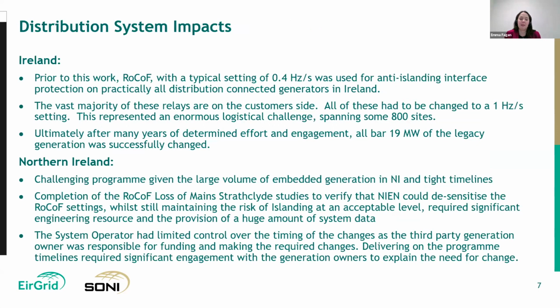One of the main impacts in Ireland was that a typical RoCoF setting of 0.4 hertz per second was used for anti-islanding interface protection on pretty much all distribution-connected generators in Ireland. The vast amount of those relays were on the customer side, so over 800 sites had to have their settings changed. This was a massive undertaking by the DSO. It happened over multiple years, and it was an amazing achievement that we got everything up, with the exception of only a small amount of megawatts of legacy generation, and that had their settings successfully changed.